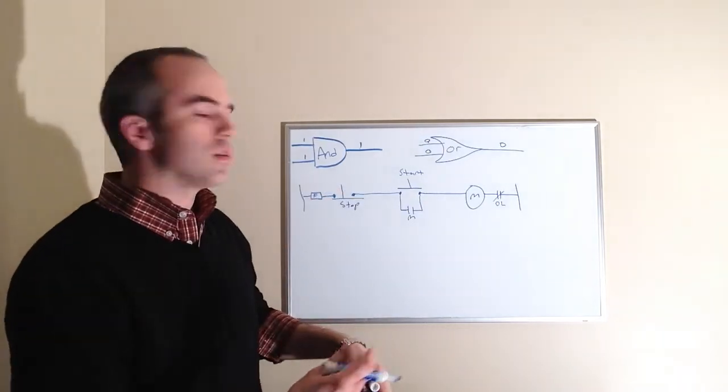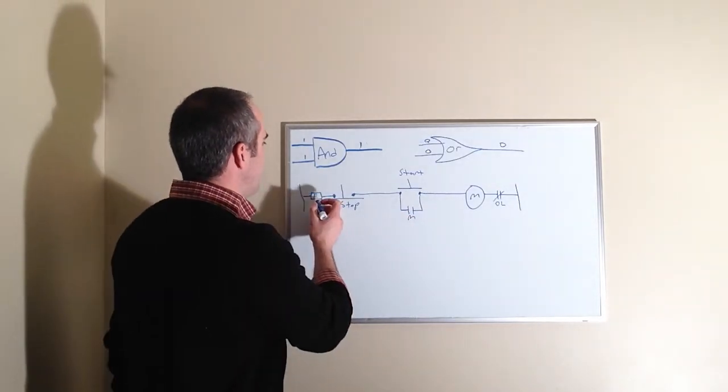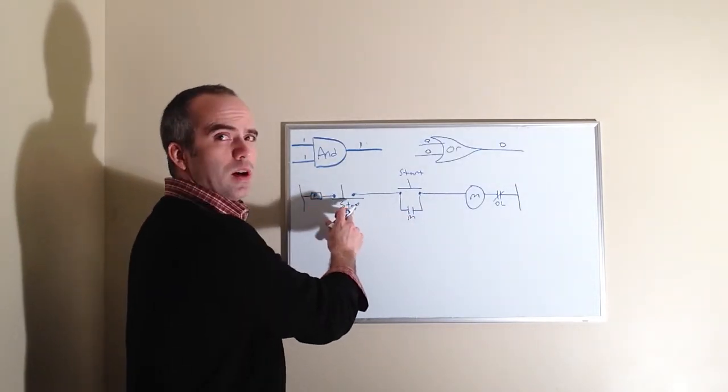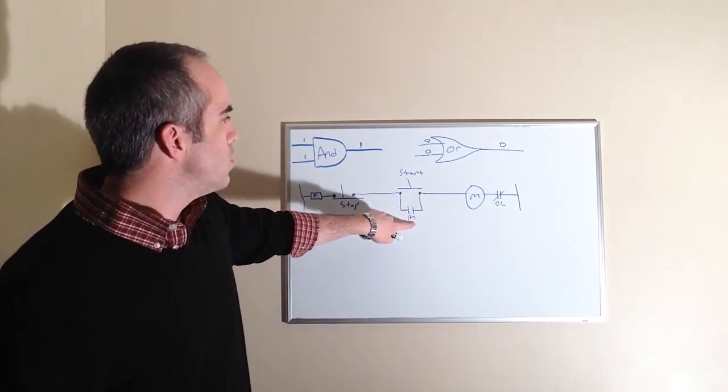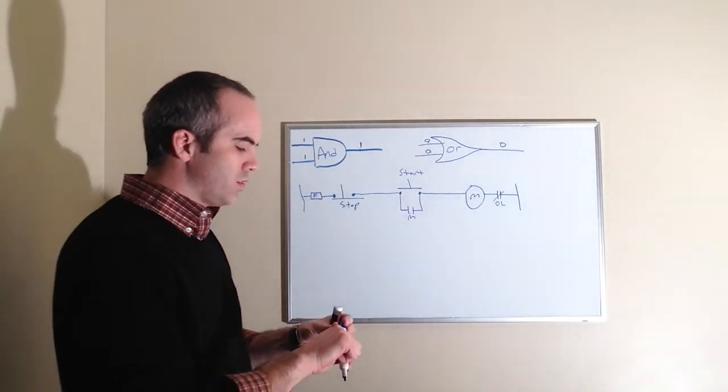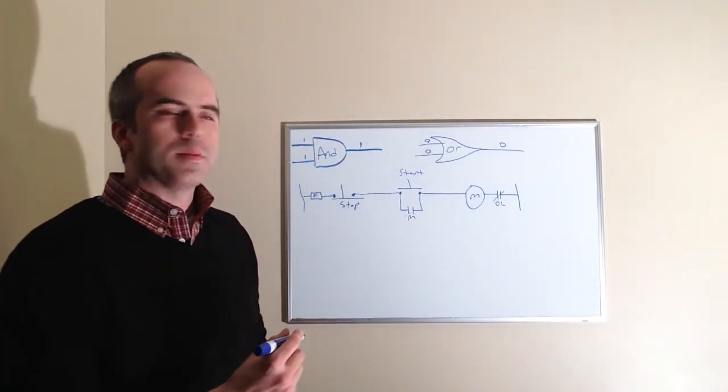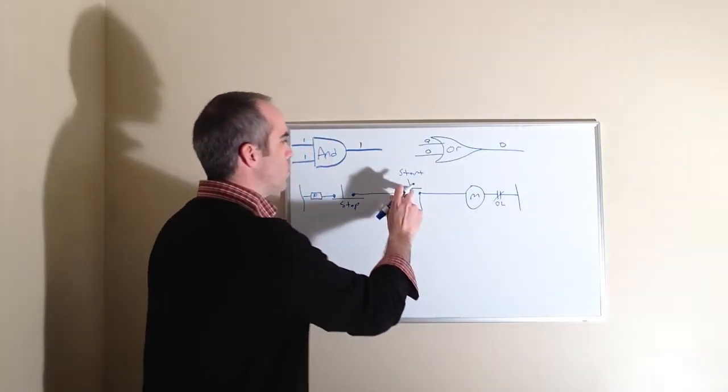If we look at our start-stop circuit, we have a series circuit, but we have this parallel loop right here. So we have a fuse and a stop button and a start button or the M-coil and the overloads. So let's draw this in a logic diagram and let's see what it looks like.